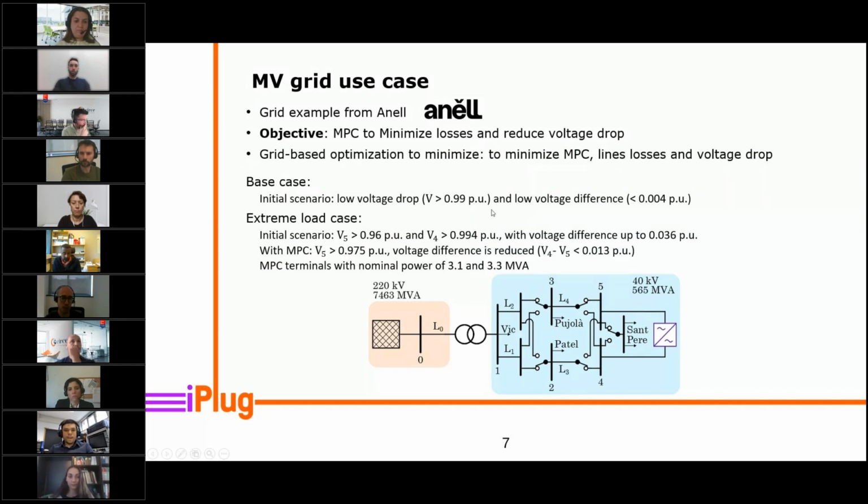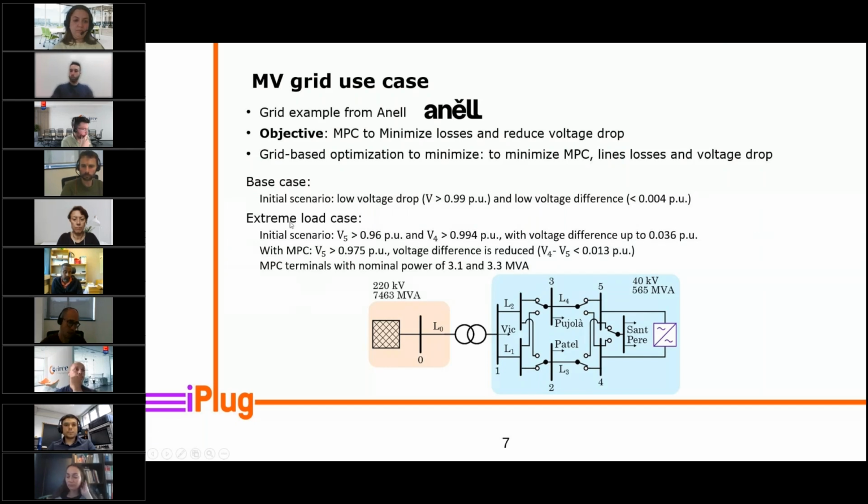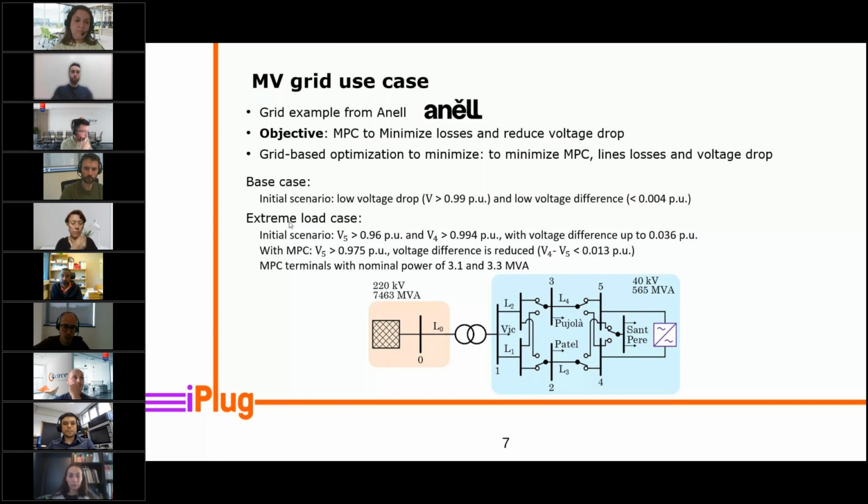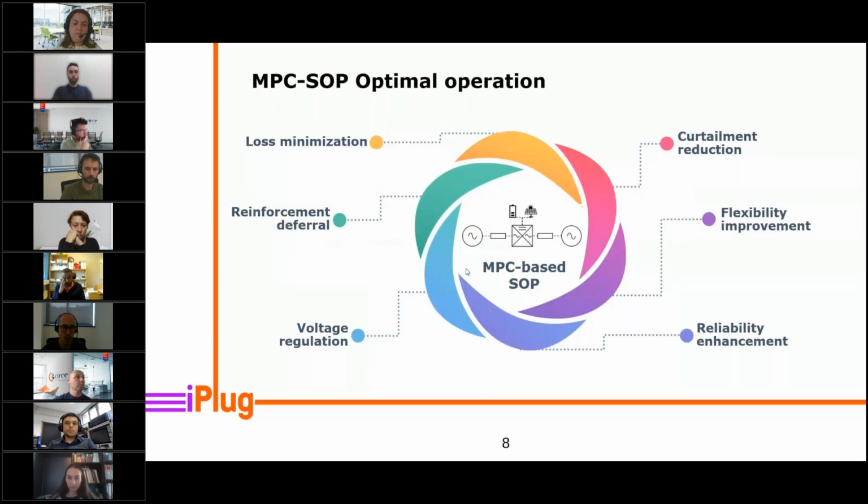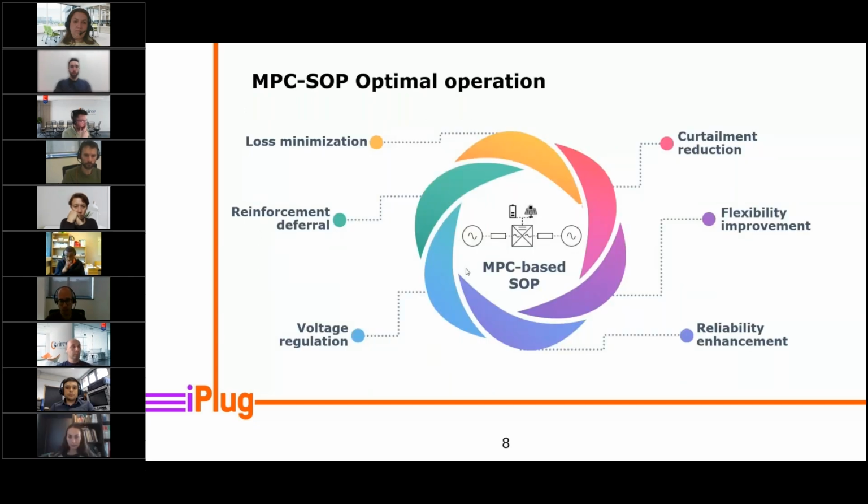And here we have done this as an example where increasing the load is where we see most of the problems, and what we could achieve was a decrease of around 3% of the voltage. And in this case, the converter that we're sizing, we are talking about a few MVAs, so it's between 10 and 100 times more than the previous cases I presented. So for this part, I will hand this over to my colleague, Antonio.